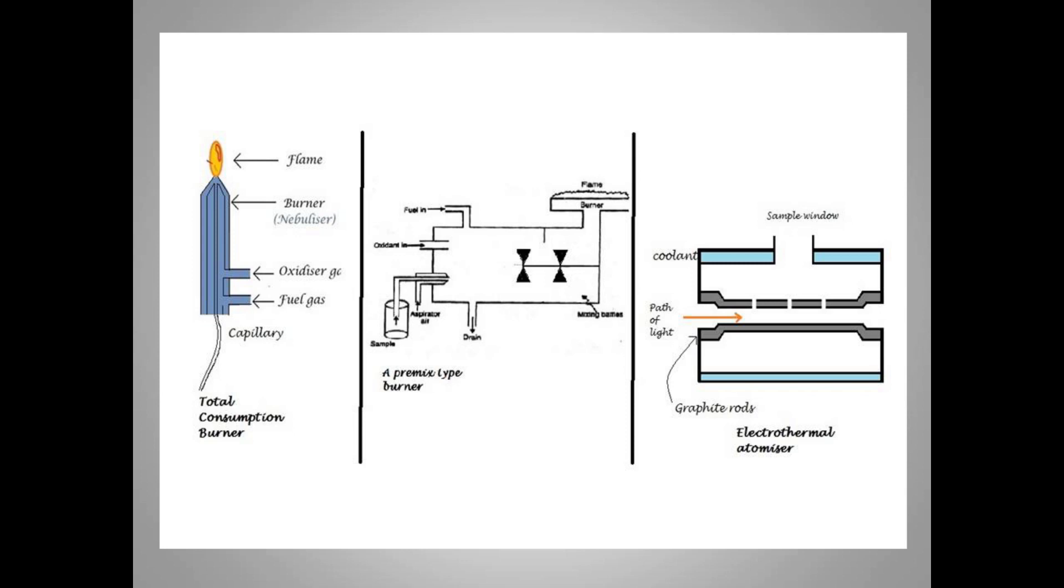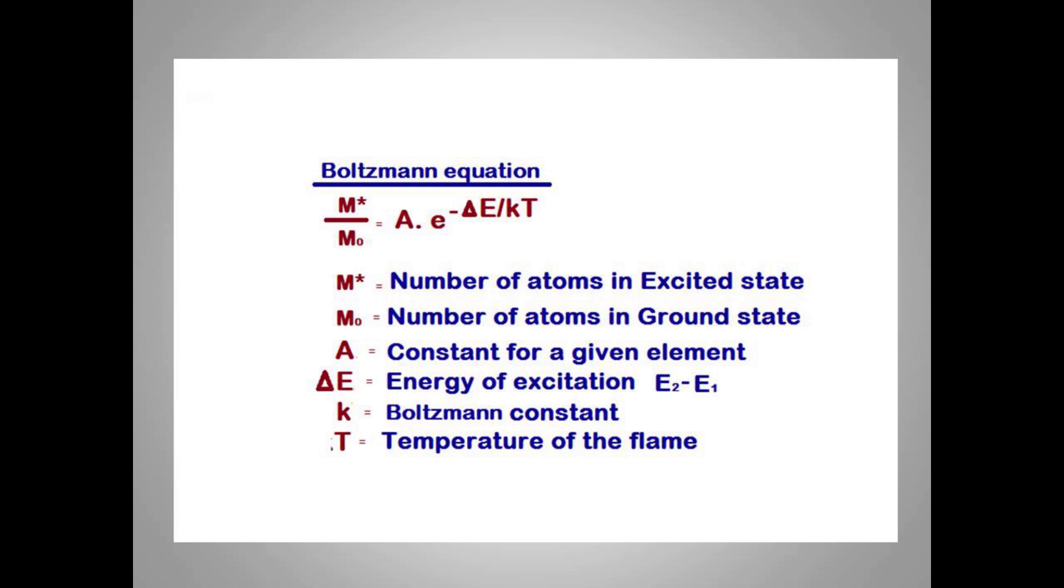Coming back to the earlier burners, they are having the combination of oxidizer gas and fuel gas because the atomization requires a very high temperature, approximately 3000 degrees Celsius. The combination of fuel along with oxidizer gas can produce a high temperature flame. Flame photometry has one limitation: it is a temperature dependent technique. In emission spectroscopy, the atom in excited state is responsible for the emission. As you can see in the Boltzmann equation here, the ratio of metal in excited state to the ground state is dependent on the temperature of the flame. Higher the temperature, more is the number of atoms in the excited state.